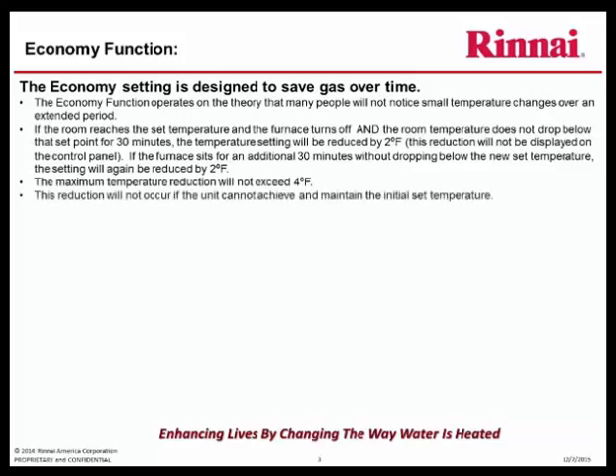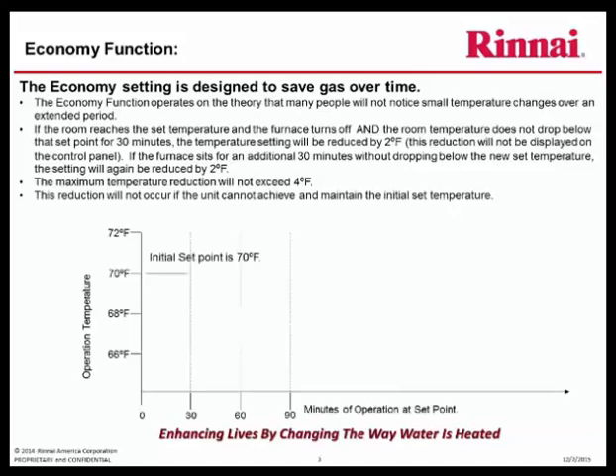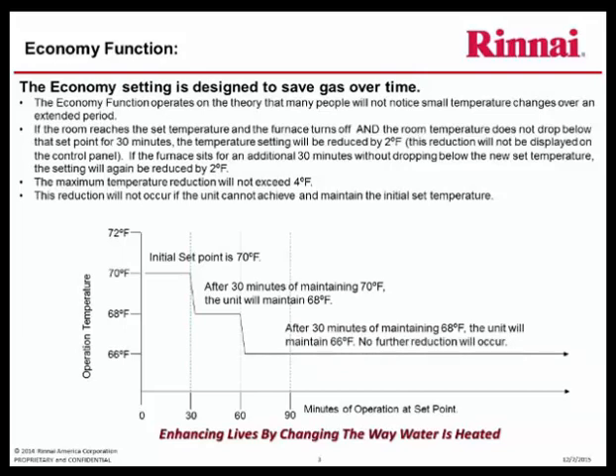This reduction will not occur if the unit cannot achieve and maintain the initial set temperature. For example, we have an initial set temperature of 70 degrees. After 30 minutes of maintaining 70 degrees, the unit will drop the set temperature and maintain 68 degrees Fahrenheit. After 30 minutes of maintaining 68 degrees, the unit will drop the set temperature again and maintain 66 degrees. At this point, no further reduction will occur.